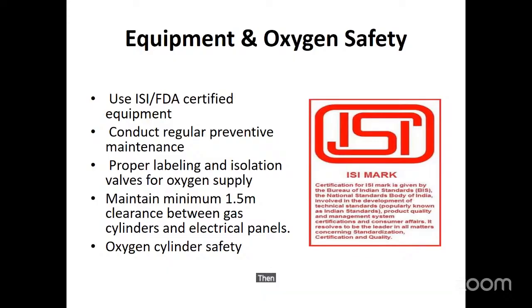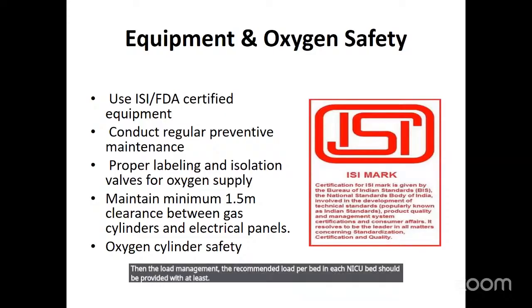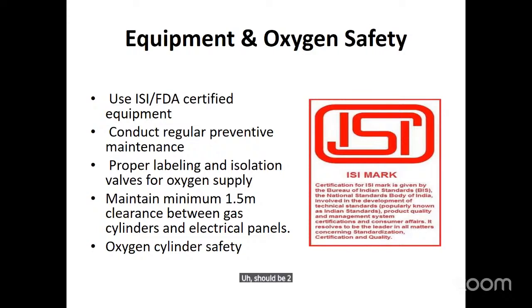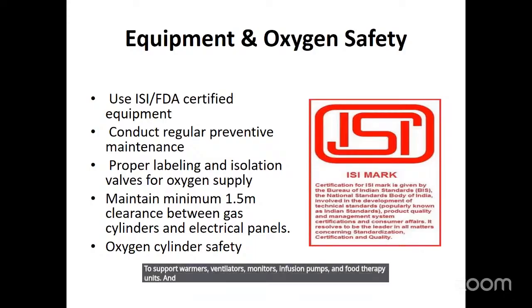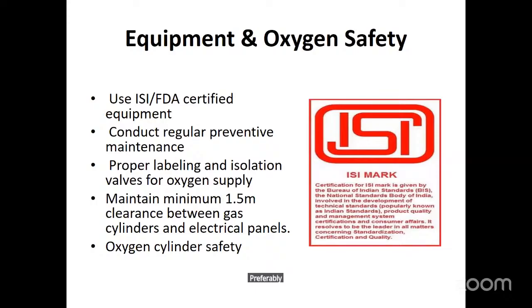Then the load management: each NICU bed should be provided with at least 2 to 2.5 kilowatt per bed to support warmers, ventilators, monitors, infusion pumps, and phototherapy units. And each NICU bed should be provided with at least 4 to 6 electrical outlets, preferably of hospital grade quality.